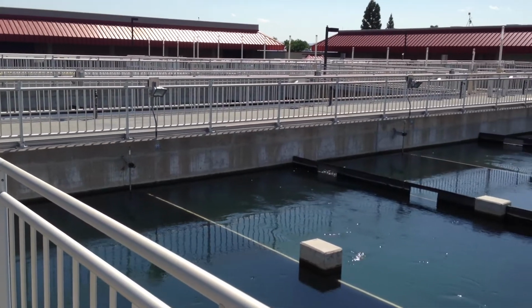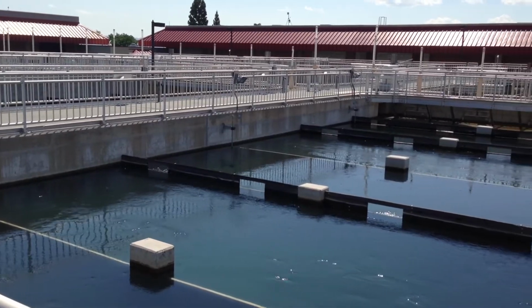And the water is very clean, but when you're talking about anywhere from 30 million gallons of water a day to 90 million gallons of water a day, it's a lot of sediment accumulation that we have a treatment process for. That's stage 1. Stage 2 is a rapid mix stage, and essentially imagine a giant blender. We're adding our coagulant to the raw water so that we can disperse that chemical into the water, get those particles to start colliding, neutralize the charges, get them to essentially disperse, and so we can remove them a little bit better down in the treatment process.